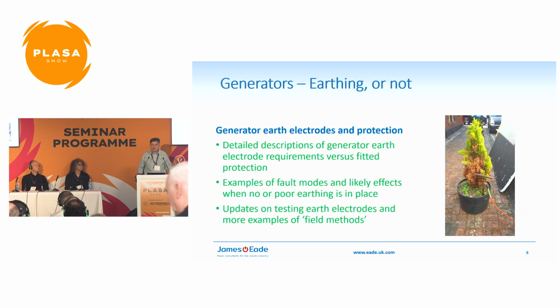The generator earth electrodes and protection, again, this builds on work that's been done at the practitioner's guide, and the relationship between the generator earth electrode values and the protection on the output has been explained, and so one can ascertain what earth electrode values you need compared to the protection you have on the output, and how the two are related between them. Again, examples of fault modes, and classics are a bad earth electrode, and then you have an insulation failure on a cable making the ground live. So things like that are explained, and the symptoms are depicted in the pictures in the book to help people understand and reinforce that relationship between the earth electrodes and the protection.